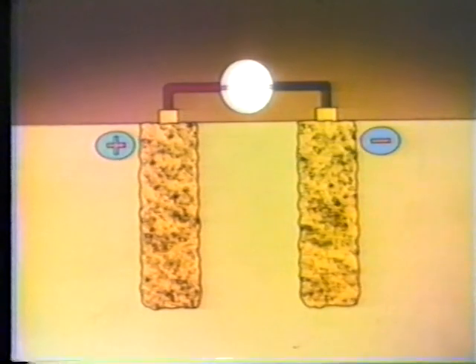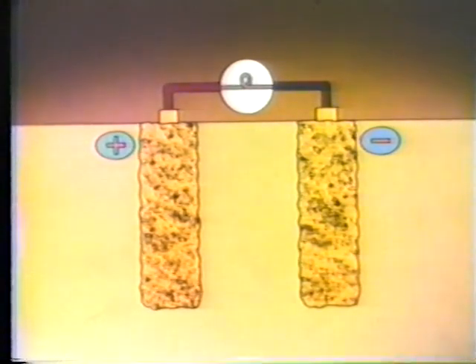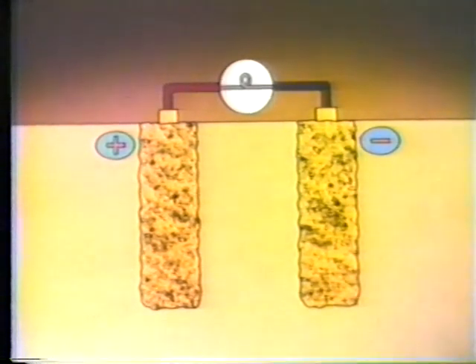Since the sulfuric acid electrolyte is the source of the sulfate, the electrolyte gradually becomes watered down. When the cell is completely discharged, both plates are pure lead sulfate, and the electrolyte is mostly water with only a small amount of sulfuric acid in solution. In this condition, the cell is no longer capable of supplying electricity — its stored chemical energy is used up.